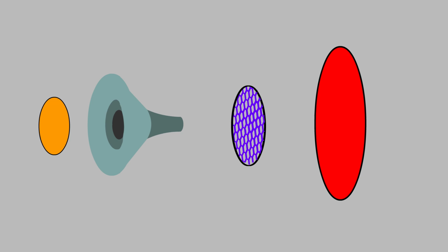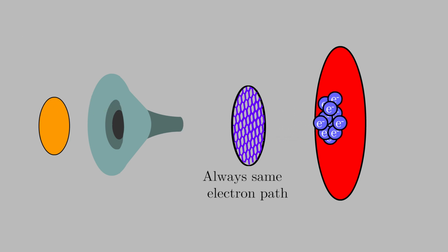But experiments in the quantum world require extreme precision. In a quantum experiment, the exact picosecond a photon arrives is critical, and the randomness of transit time spread is our biggest enemy. To fix this, the device is shrunk. The focusing electron paths are tightened, and in advanced models like microchannel plates, the distance between multiplication stages is reduced to microscopic levels.